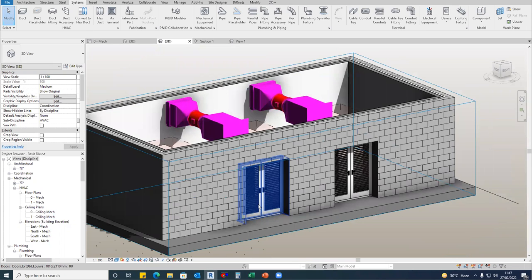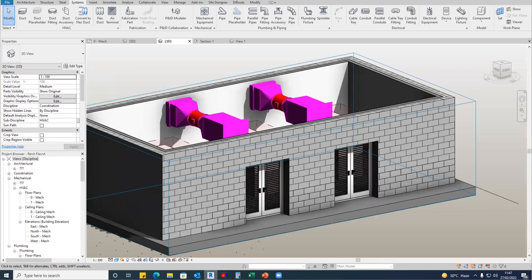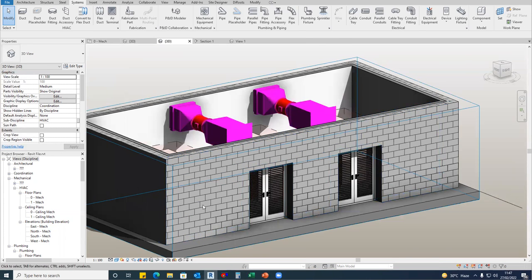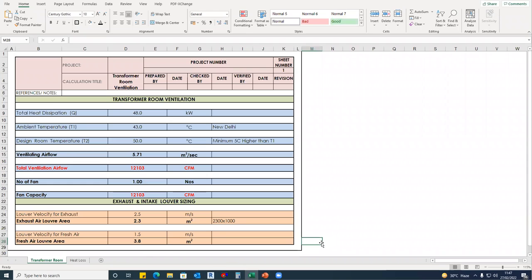Okay, for example, we consider there is no louver door. In that case, what you have to do, for example, we have a 3.8 meter square requirement. So what I'll do, half the area of fresh air I'll take from this wall, and half I'll take from this wall. So 3.8 divided by 2, that is 1.9, means 2 square meter from one side, 2 square meter from the other side. Okay, so the size for 2 square meter will be 2 meter by 1 meter, two numbers. Okay, two numbers of fresh air louver of size 2 meter by 1 meter.